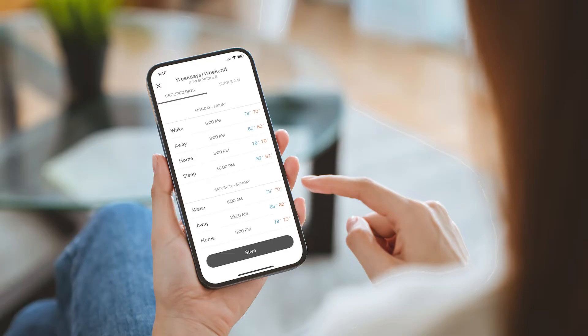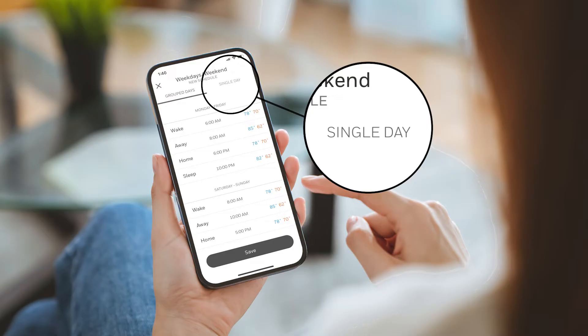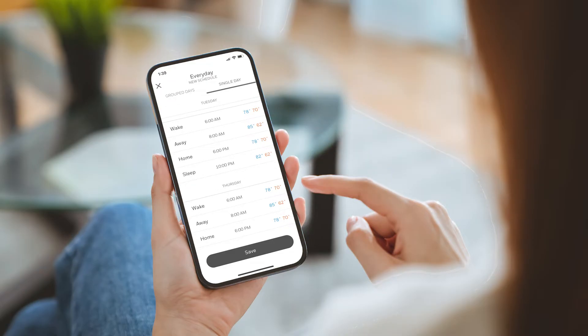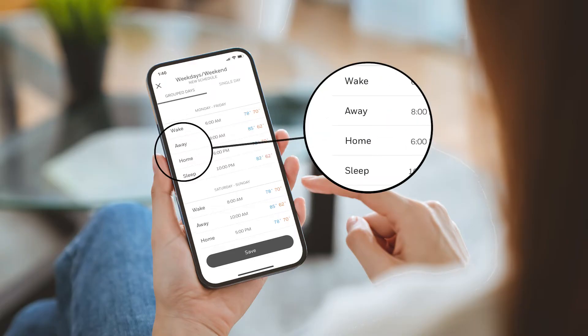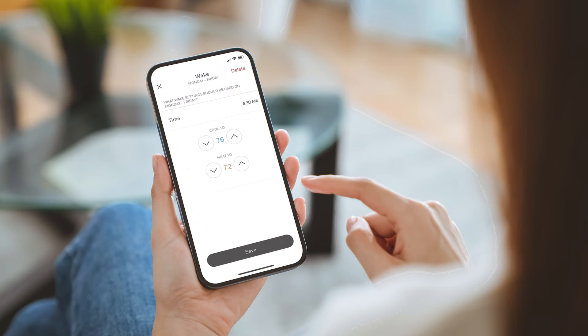Here, we're showing programming for group days. You can also program settings for individual days under the single days tab. There are four adjustable periods for each day. Let's start by adjusting the wake period for Monday through Friday. Tap wake and set your wake schedule start time in 15 minute increments. Then use the up and down arrows to set your desired cool to and heat to temperatures for the morning. Tap save.